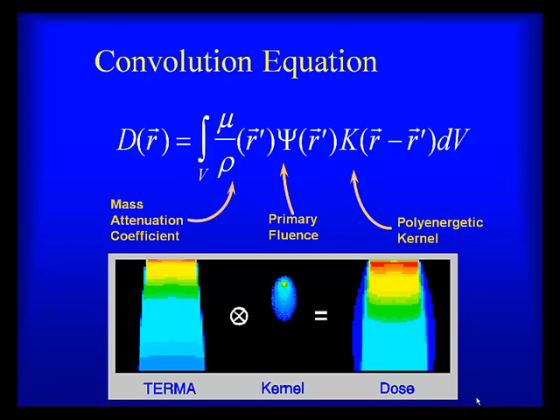The second class of model-based algorithms is convolution superposition, the most popular in current treatment planning systems. This is the heart of most popular planning systems — including Pinnacle, Eclipse's AAA algorithm, Oncentra, Tomotherapy, and research systems. Mathematically, the dose is expressed as an integral: the sum of the mass attenuation coefficient times the primary photon fluence times a convolution kernel.